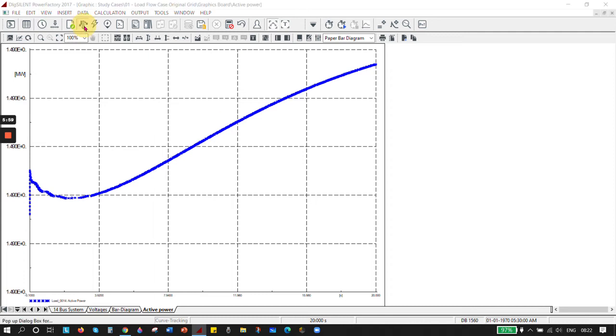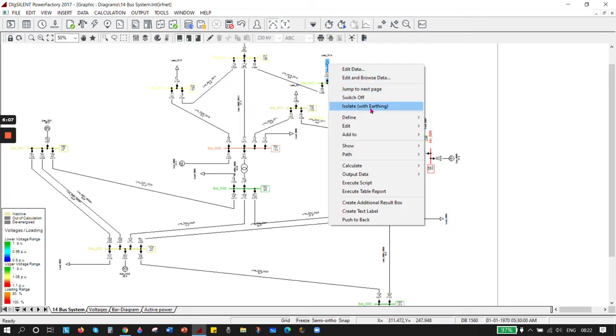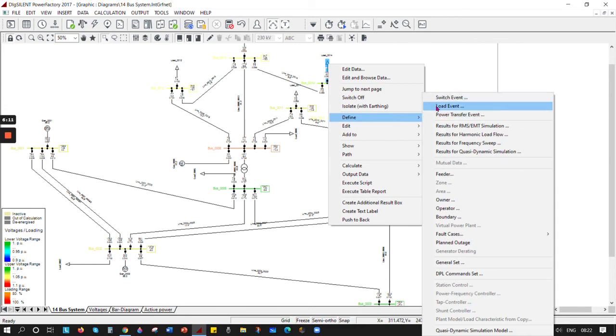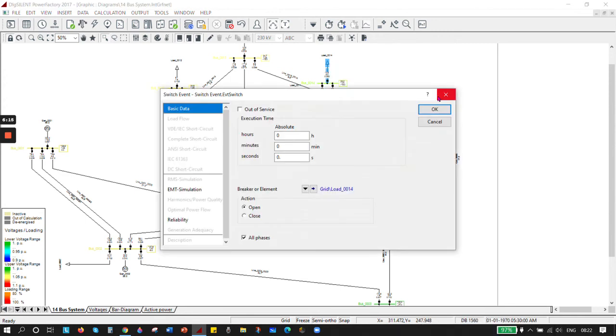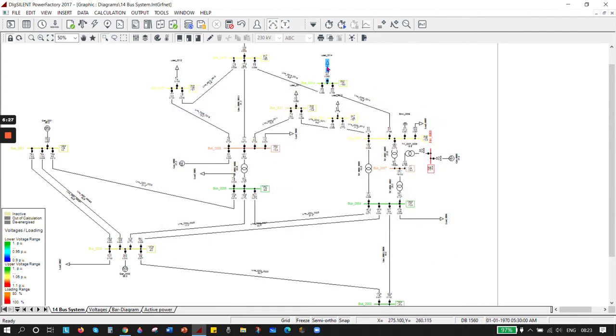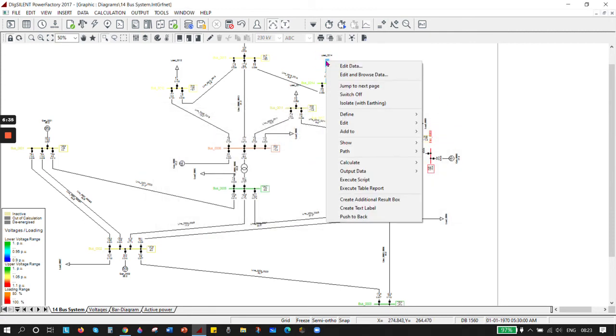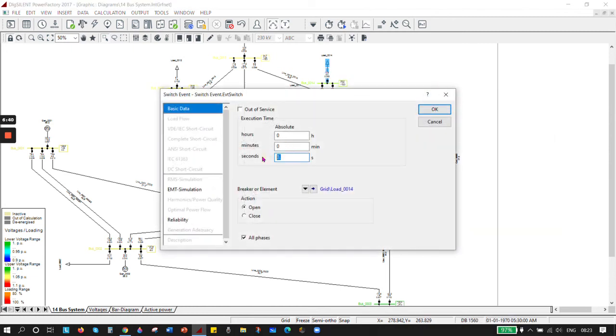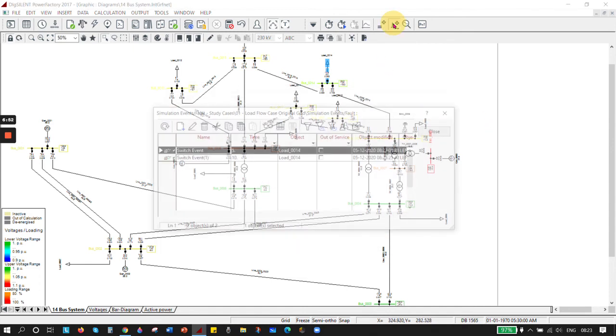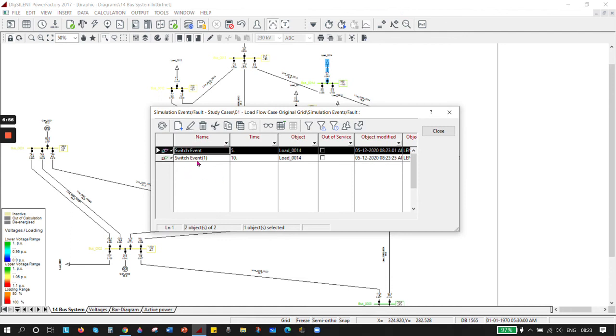Go back and run the load flow, then go back to the system. Select the load, right-click, choose 'Define', and you can choose either a switch event, load event, or transfer event. I'm doing a switch event - I want this to switch at 5 seconds with the breaker open. Click OK. You will see the switch event appear. Then define another switch event to close it again at 10 seconds, and click 'Close'. Press OK.